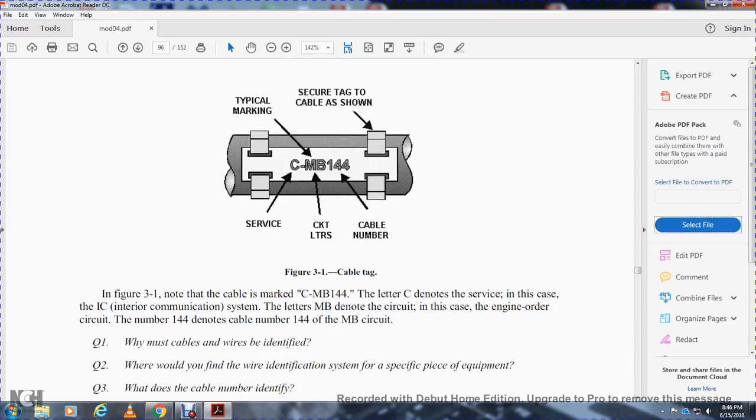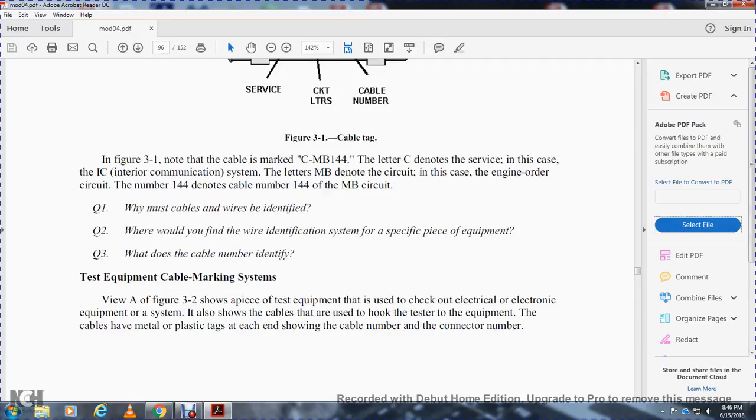In figure 3-1, the cable is marked C-MB144. The code 'C' denotes the service — in this case, internal communication systems. 'MB' denotes the circuit, which is the engine order circuit. The number 144 denotes the cable number within the MB circuit.